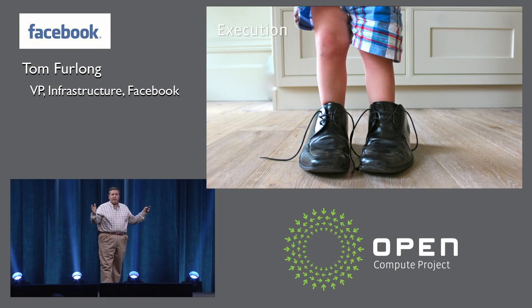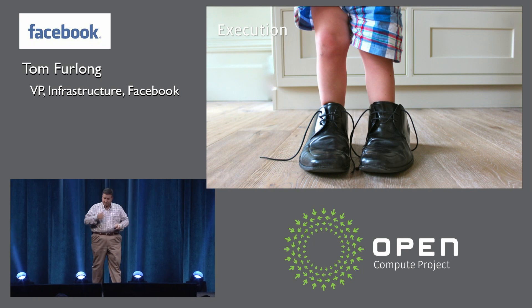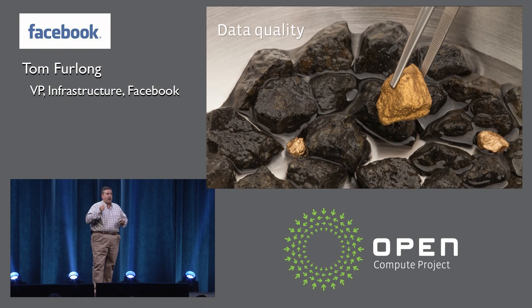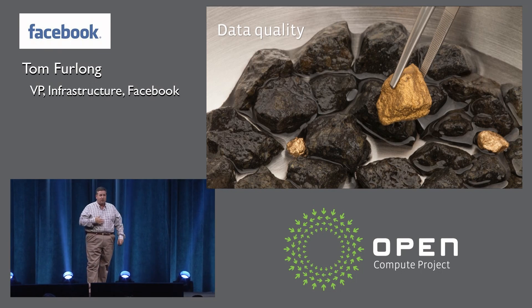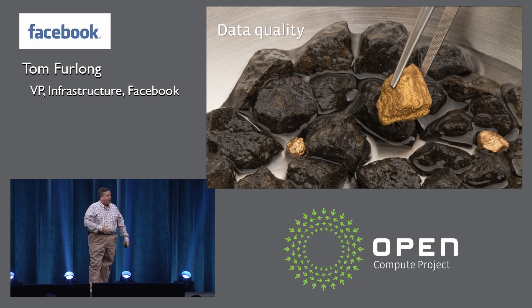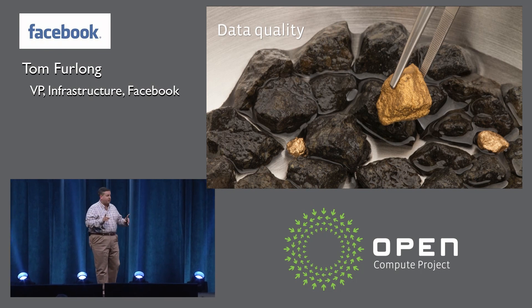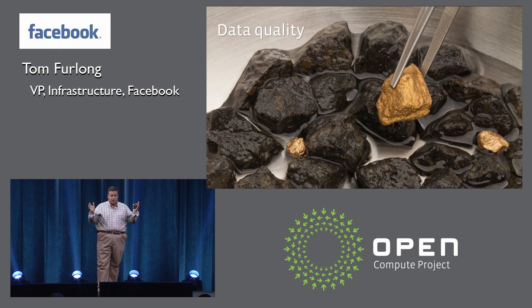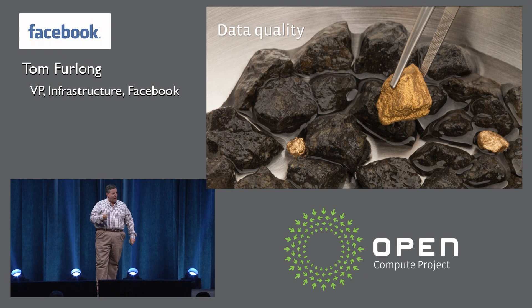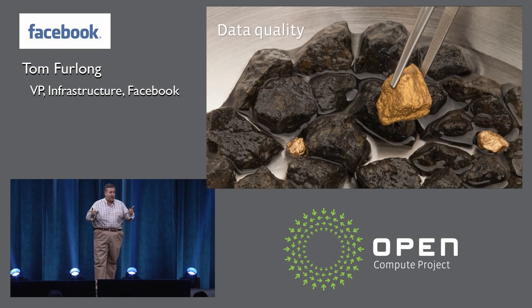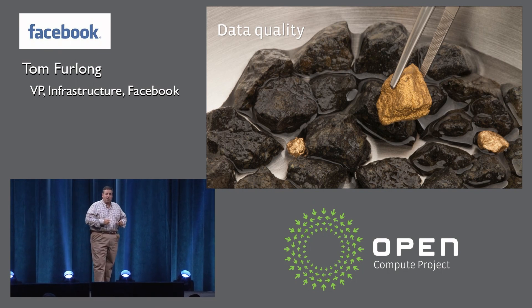We implemented a further step called a pilot program — soup to nuts, one data center building: Prineville 1. I wanted everything in that building, to show we could get it into our system. It doesn't have to be a hundred percent perfect, but we proved that it works. This was a truly valuable lesson because we learned how important data quality was. We have six buildings completed or under construction and I like to feel we've done a good job maintaining consistency across them, but no matter how hard we've tried, it's not perfect. Every single facility you need to look at in nauseating detail to make sure the data is correct. For example, one building has an Alerton system, another has Siemens — and one presents data in kilowatts while the other presents data in watts, so one data source comes out a thousand times larger than the other.